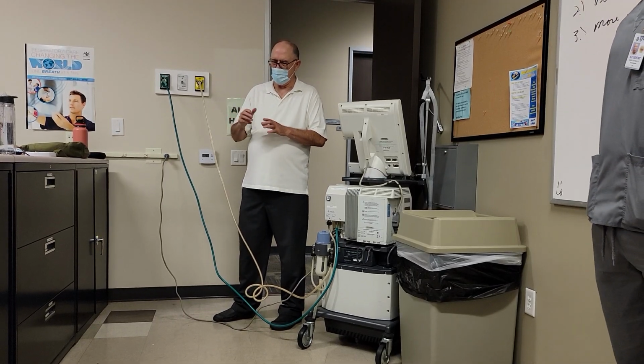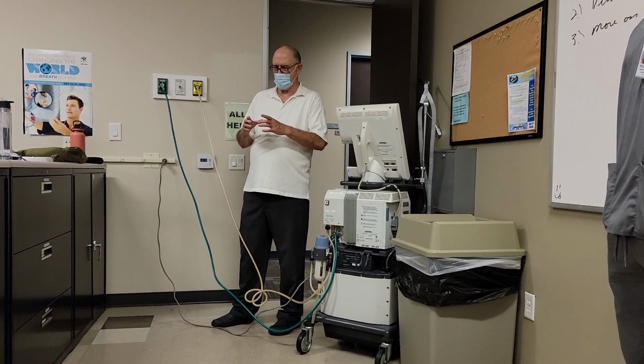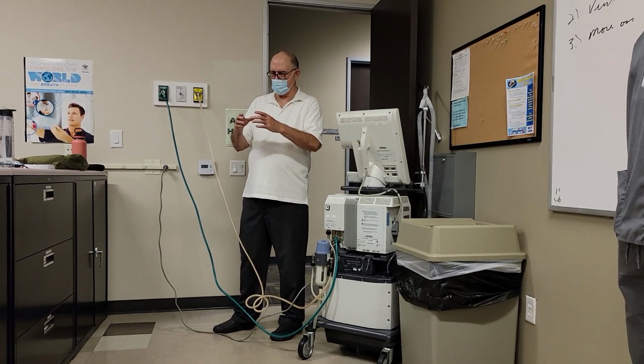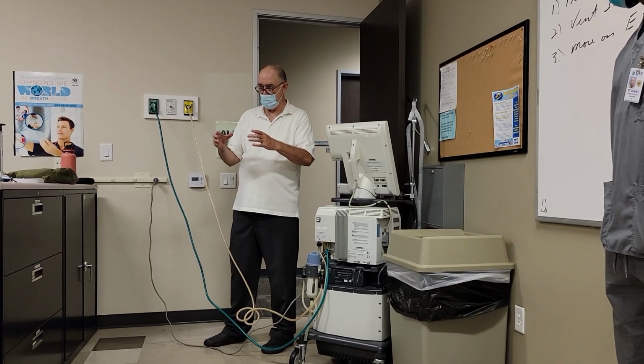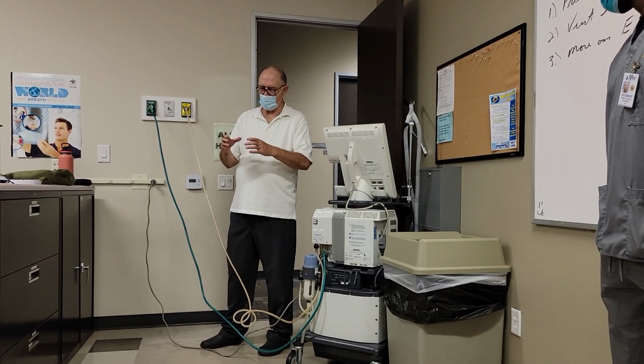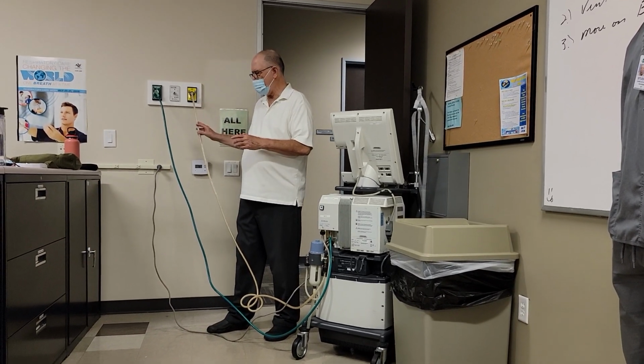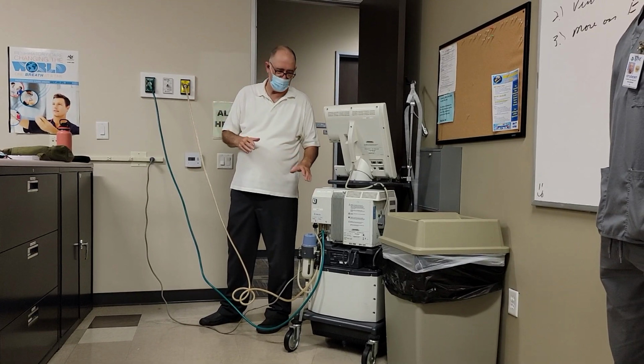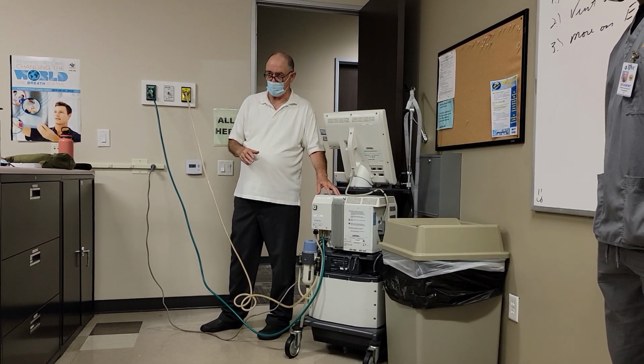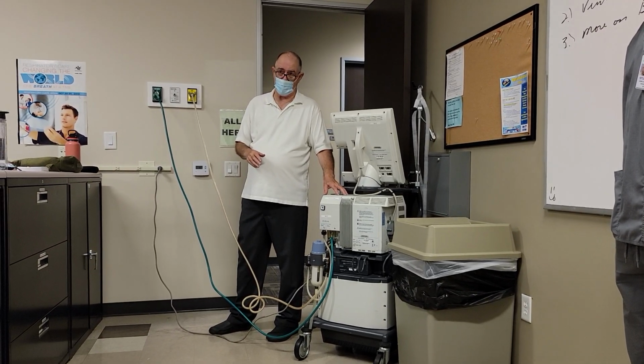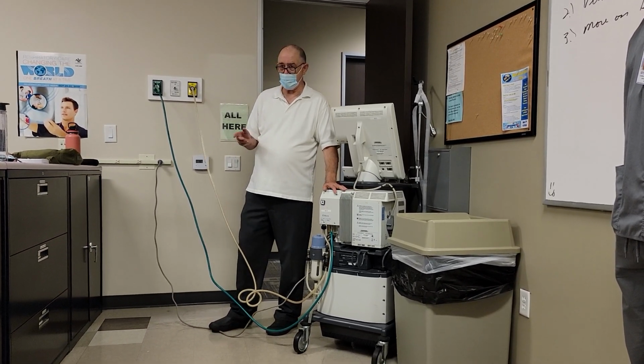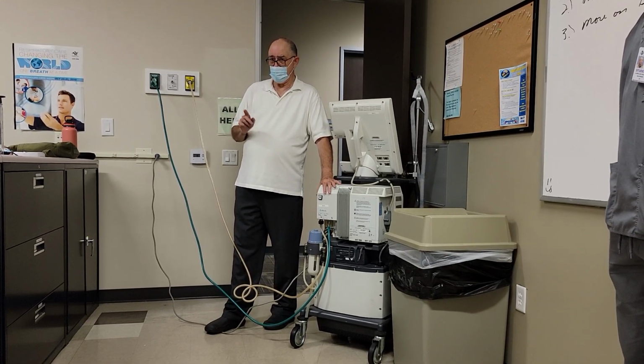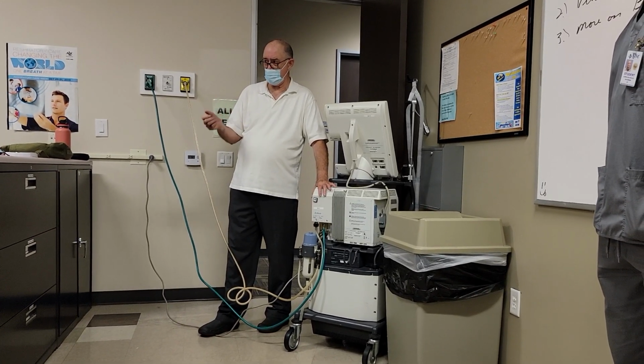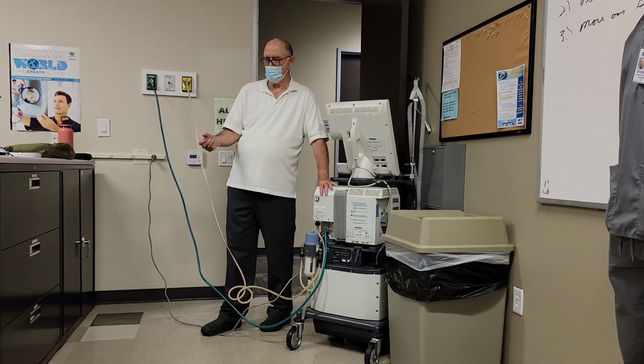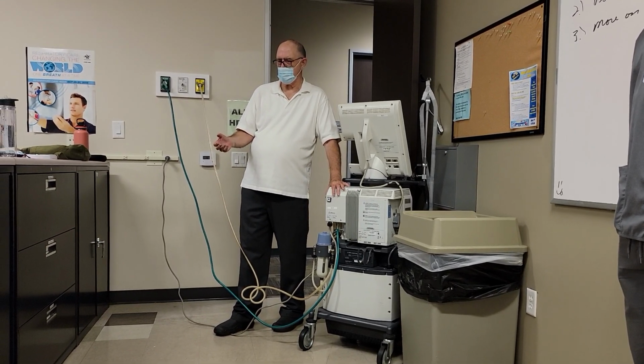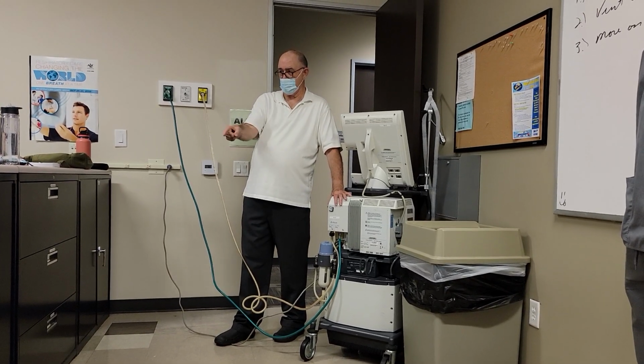On the other side of the blender is the internal pneumatics, okay? And in the internal pneumatics, the 50 PSI is brought down to the operating pressure in the ventilator, which will still be somewhere, as in this one, greater than 10 PSIG. 10 PSIG, if you were to take a hose, like a fire hose, or a gardening one that you just squeeze and stuff comes out.